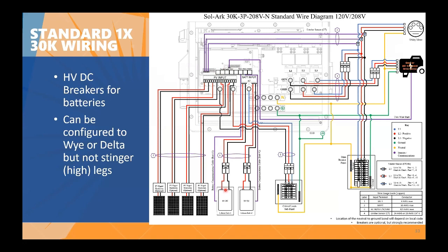The high voltage batteries, as you can see depicted in the diagram, you can use 2 of them separately into each battery input in the Sol-Ark. And the battery communication, just as I mentioned before, you can connect those through the BMS. You can as well connect the grid directly to the grid port in the Sol-Ark. And as I mentioned before, you can connect a generator, microinverters, or any other AC coupled solution in this port of the inverter.